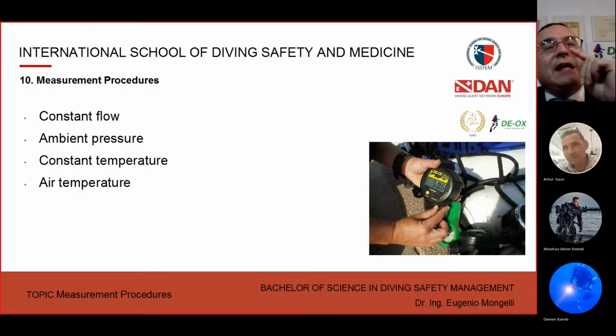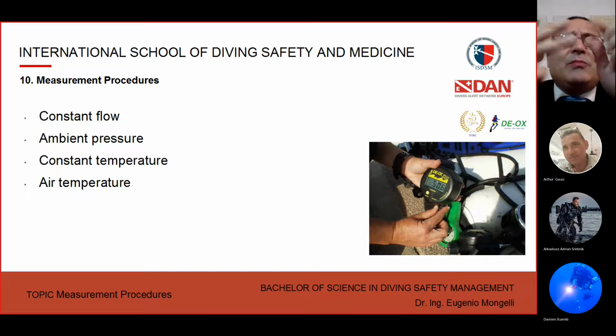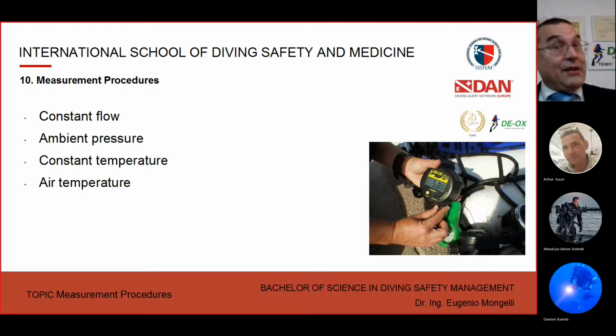Yes, you're right. Because in theory, if you have constant pressure, constant temperature, constant flow, stable, in a laboratory, and so on, if you calibrate the sensor well at 21%, there is no reason why you would not have the best accuracy also at 100%, close to 100%.